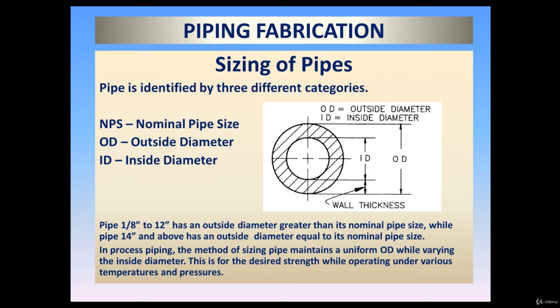Nominal pipe size is used to describe a pipe by name only. In process piping, the term nominal refers to the name of the pipe. Outside diameter and inside diameter, as their names imply, refer to pipe by their actual outside and inside measurements. Pipe from 1/8 inch to 12 inch has an outside diameter greater than its nominal pipe size, while pipe 14 inch and above has an outside diameter equal to its nominal pipe size. In process piping, the method of sizing pipe maintains a uniform outside diameter while varying the inside diameter. This method achieves the desired strength necessary for pipe to perform its intended function while operating under various temperatures and pressures.